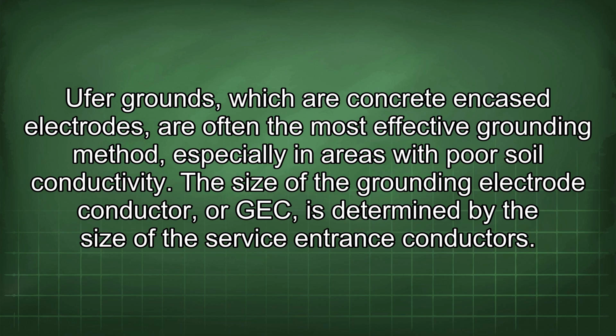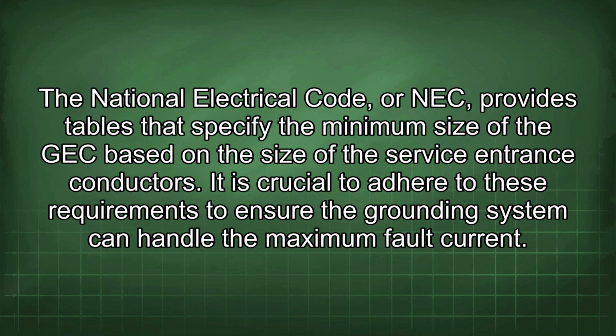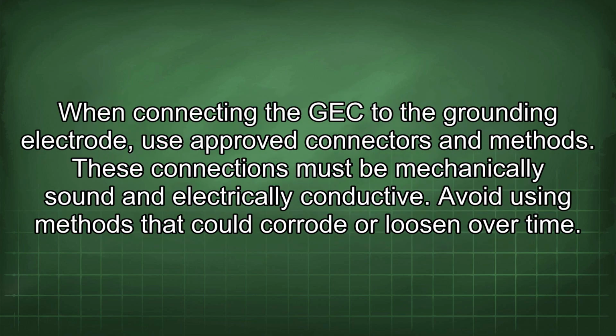The size of the grounding electrode conductor, or GEC, is determined by the size of the service entrance conductors. The National Electrical Code, or NEC, provides tables that specify the minimum size of the GEC based on the size of the service entrance conductors. It is crucial to adhere to these requirements to ensure the grounding system can handle the maximum fault current. When connecting the GEC to the grounding electrode, use approved connectors and methods. These connections must be mechanically sound and electrically conductive.